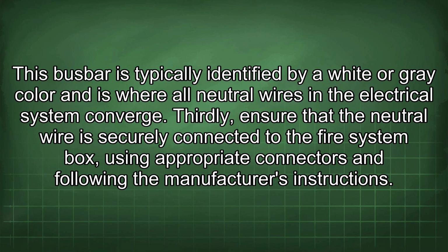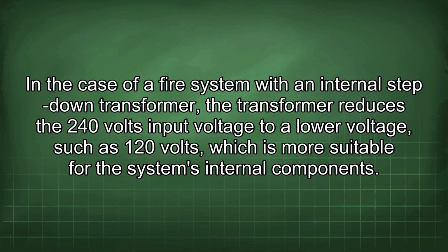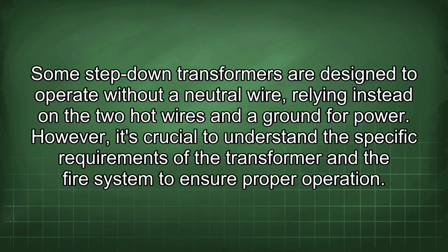and following the manufacturer's instructions. In the case of a fire system with an internal step-down transformer, the transformer reduces the 240 volts input voltage to a lower voltage, such as 120 volts, which is more suitable for the system's internal components. Some step-down transformers are designed to operate without a neutral wire, relying instead on the two hot wires and a ground for power.